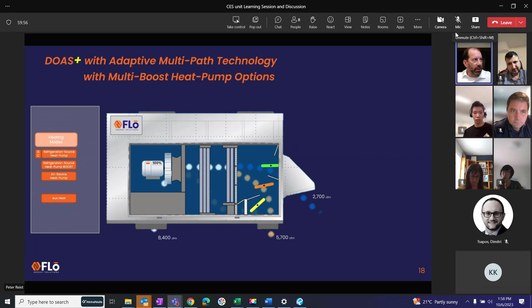Our first heating mode is where we get free waste heat from refrigeration, which we call reclaim historically in the industry. If you have a refrigeration rack, there's a refrigeration gas cooler or condenser. Typically refrigeration systems have cold cases, and they dump all their waste heat out on the roof through one of these condensers. I suppose you don't have that on the roof. What are you doing with the waste heat from your refrigeration system in the store?